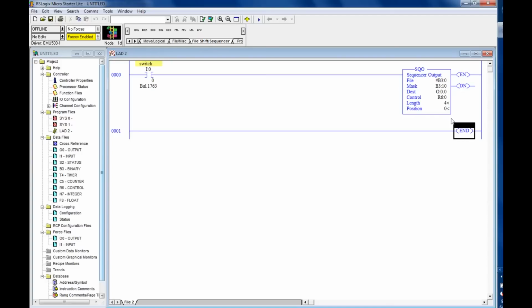There you have 12 outputs, three outputs for each direction. For all the 12 outputs, you will be connecting them in rungs. All the 12 outputs should have the necessary conditions. To reduce the number of rungs, you can make use of this sequencer block. So how do you turn on multiple outputs with a single condition? It will reduce the number of rungs if you use this block in the four-way traffic light control.